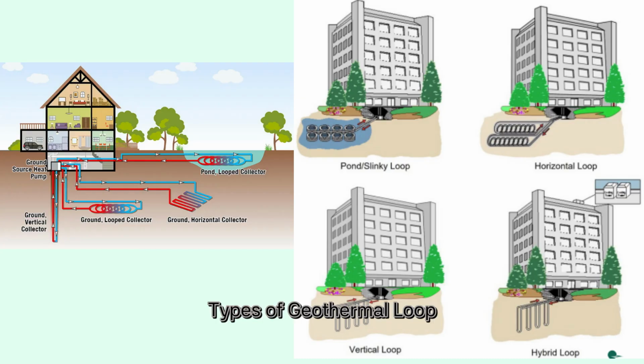Types of geothermal loop fields. Pond loop, least expensive if a nearby water body exists. Horizontal loop, installed in shallow trenches, 5 to 6 feet deep. Vertical loop, deep wells, best for urban areas with limited land. Hybrid loop, combination of geothermal wells and cooling tower for cooling dominant climates. These systems often eliminate or reduce the need for boilers and cooling towers altogether and last for decades. The underground loop typically lasts a lifetime.